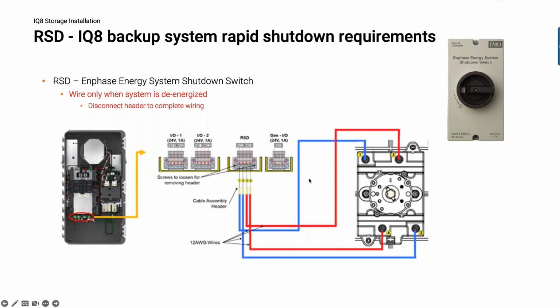When you install this switch, there are some wiring things that you have to be aware of. Now, the system shutdown switch is like a 2-pole switch here. The way that the switch works is when you close the switch, it connects these terminals, terminal 1 and terminal 2, they're crosswise, and terminal 3, terminal 4. So if you're thinking 1 is wired through to 4, it's wrong. It actually gets crossed. You have to pay particular attention to how this is wired.